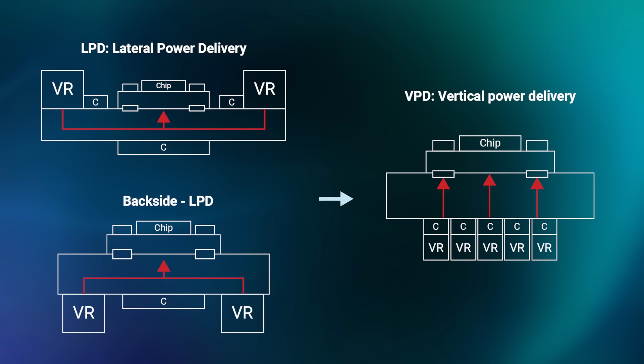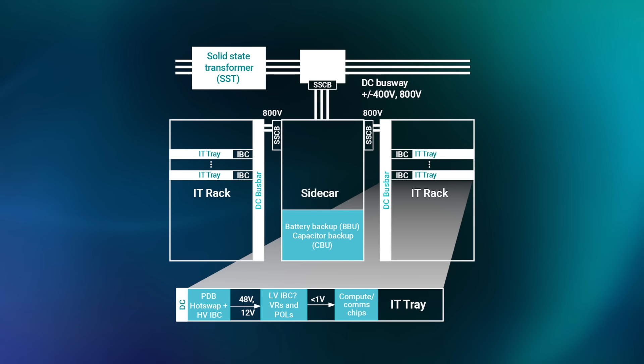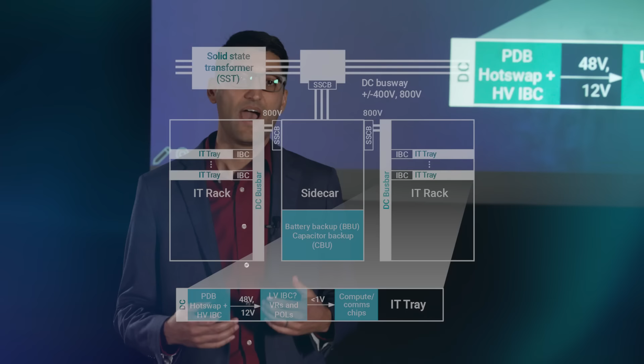As we look to the future, there are several potential future trends in how power is delivered in data centers. One of the key ones being solid-state transformers. A solid-state transformer replaces the big, bulky line frequency transformer with a much smaller, higher frequency transformer that is still efficient. It leverages power electronics to shrink the overall size, and at the same time, it enables higher voltage DC distribution in the data center. This could be at 800 volts, plus or minus 400 volts, or maybe plus or minus 800 volts.